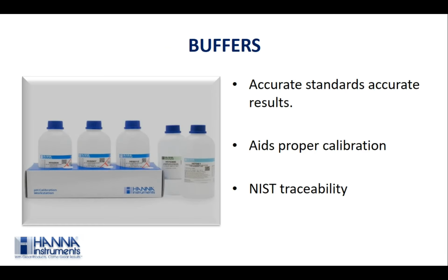When you try to calibrate your electrode, there are only three things that can cause error: the meter, the electrode, and the buffer. Each and every pH buffer has fixed millivolt readings according to its pH. Hence, we know which buffer can produce how many millivolts. Thus, in any case, if your buffer is not showing the expected pH, just calculate the millivolts and you will understand where the exact issue is.